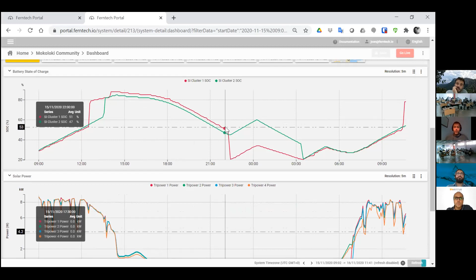As you can see here in the curve of the state of charge, it increases during the day because it's sunny. But then once people start using the loads in the afternoon or evening, the state of charge goes down, down, down. At some point, because it goes below a certain trigger value, they connect the diesel generator. That's why you see these peaks in the state of charge of the battery.